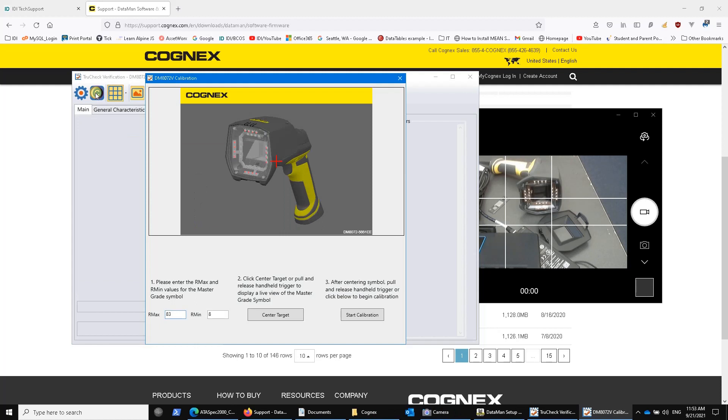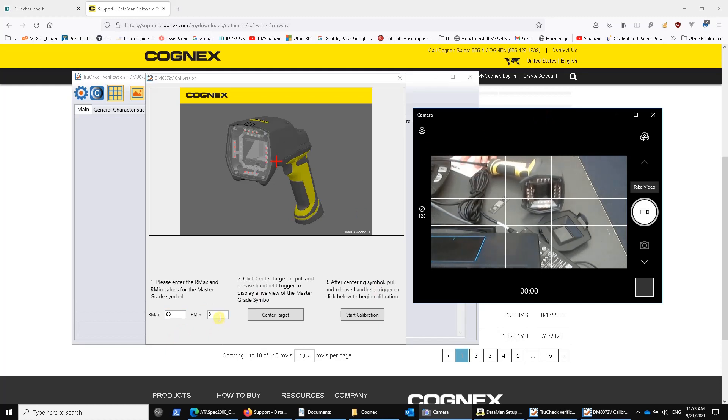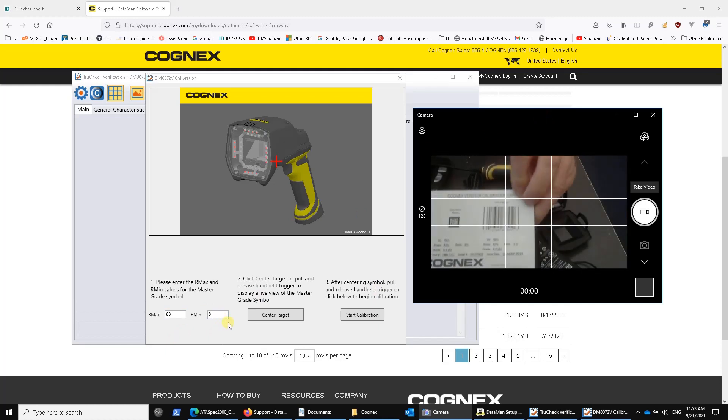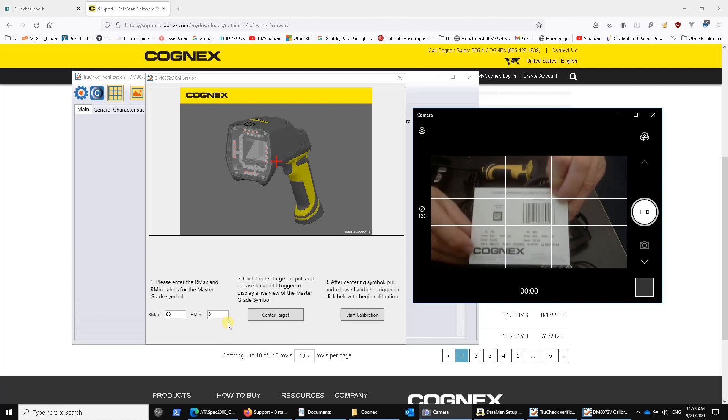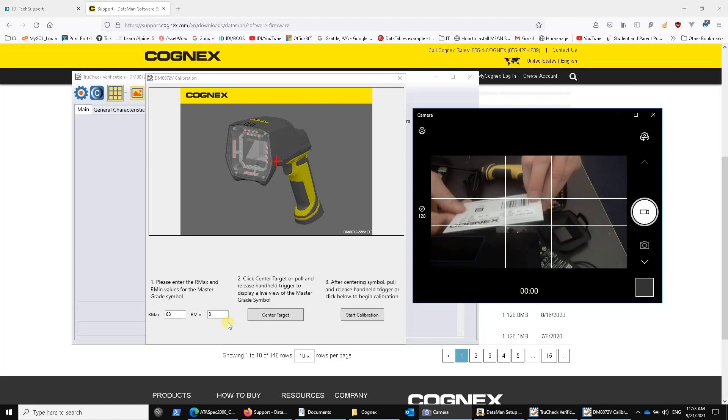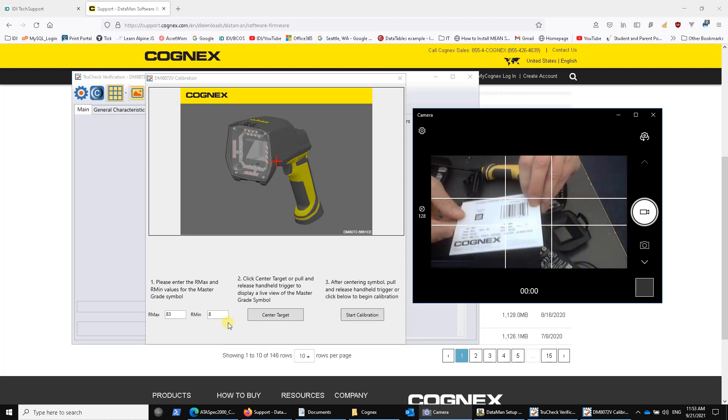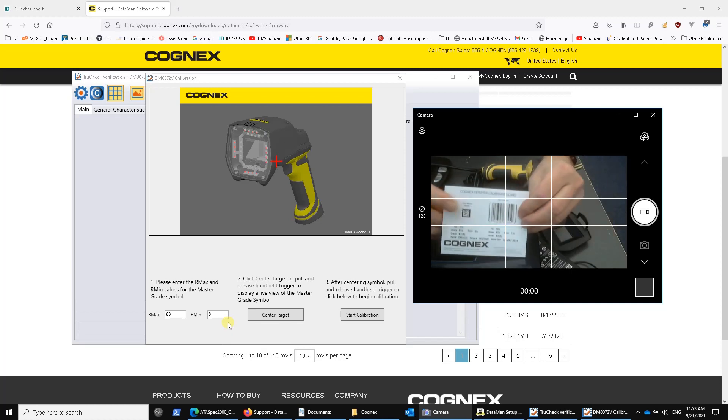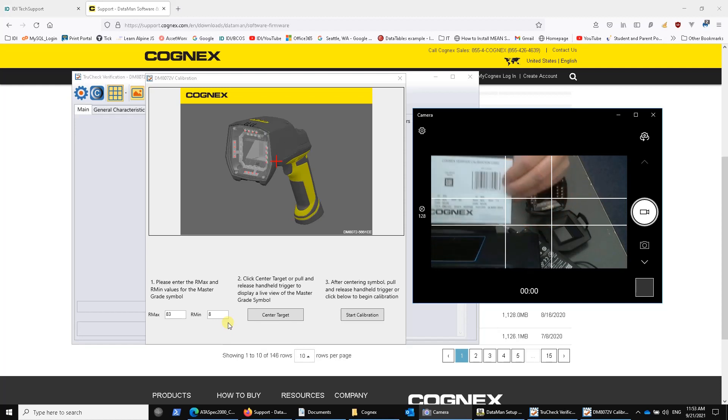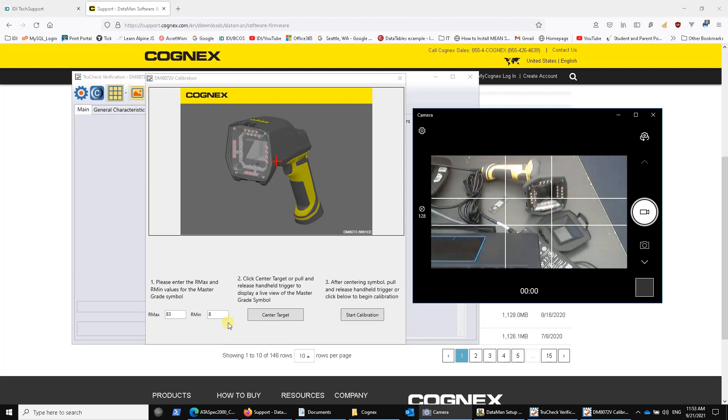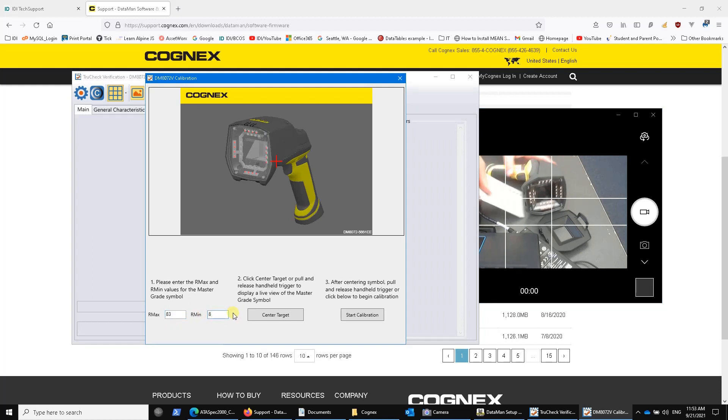All right. So with all of that, let's come back and let's go to the next step, which is calibration. So if you hit C for calibration, it's going to first ask you for what is the Rmax and Rmin values. And again, you'll see that on the Cal card. If you look at the Cal card, you'll see them like here, right, for the data matrix code. So you'll see a different number over here for this barcode. So I'm going to use the data matrix code for my calibration, so I'm going to put in those numbers. So down here, I have Rmax at 83 and an Rmin at 8. You can see I've done this before, right?